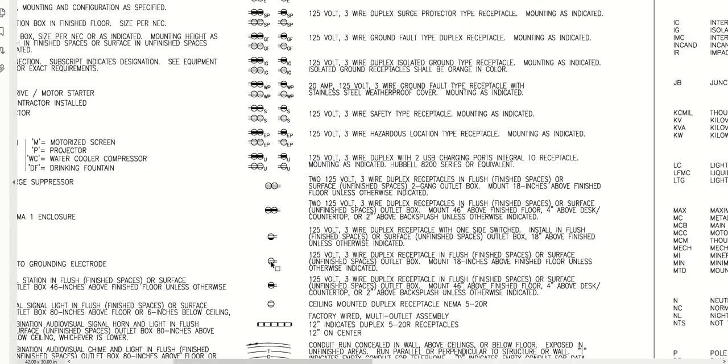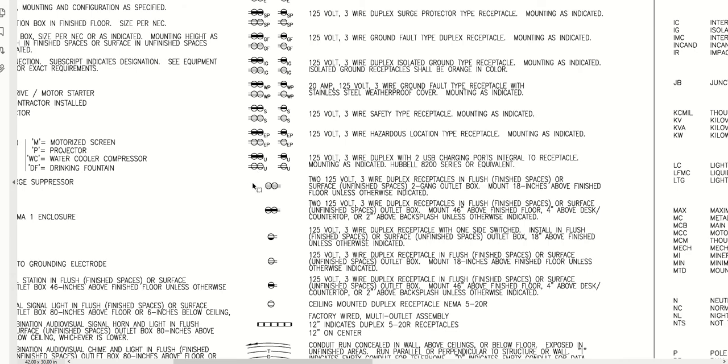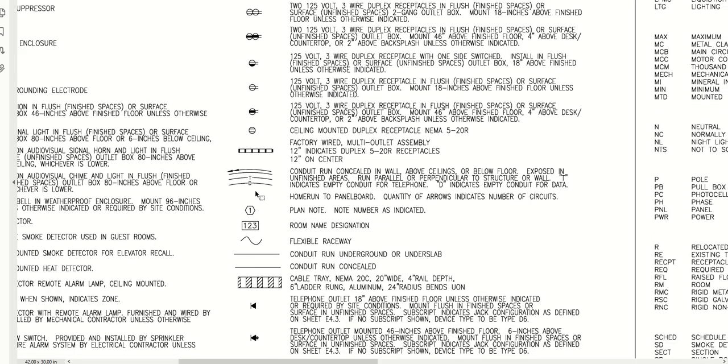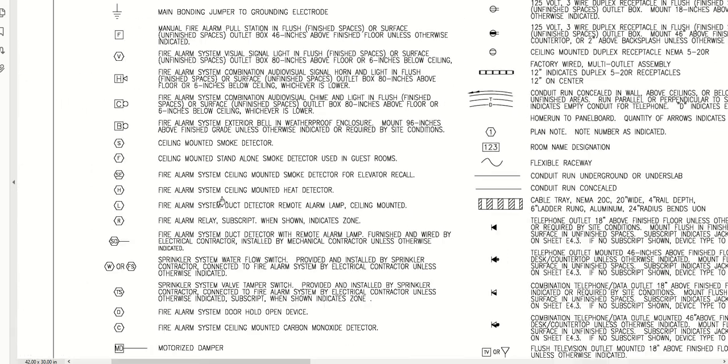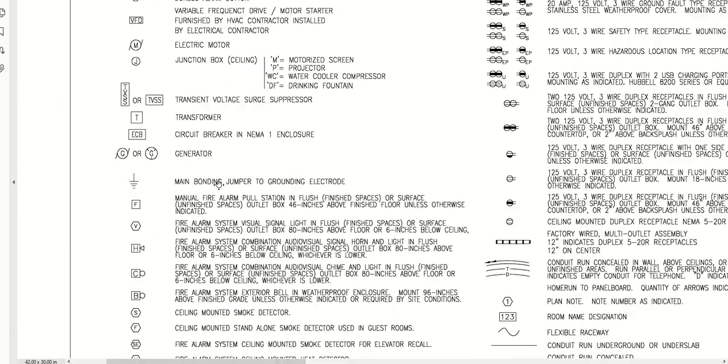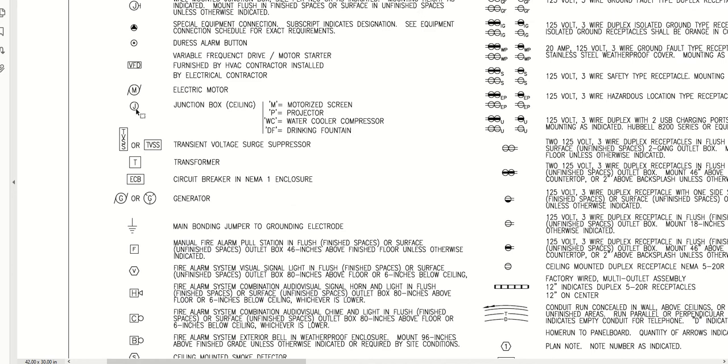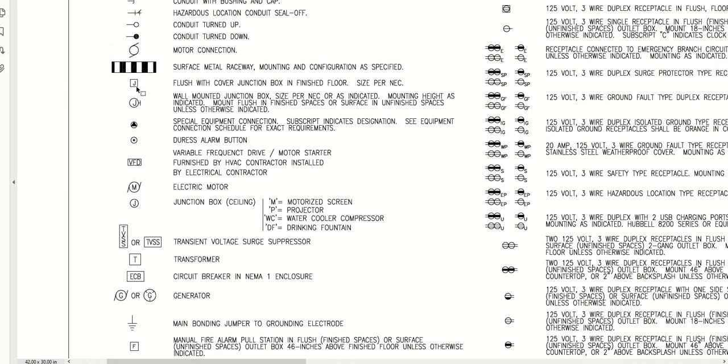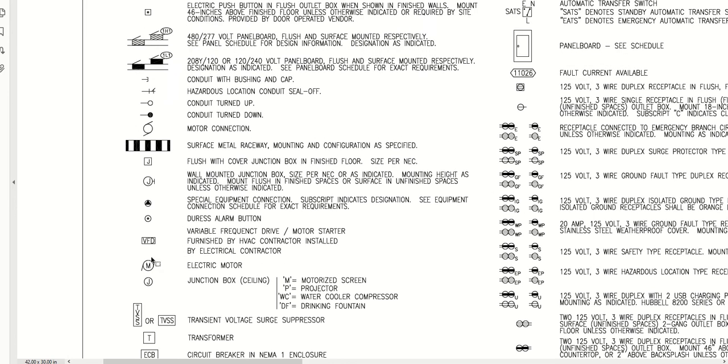We have our general receptacle outlets—these are at 18 inches. If it's filled in, it's at 46 inches. If it doesn't have the little divots, it's a ceiling mount. We have tags for weatherproof, isolated ground, ground fault, and we have junction box connections for floor, wall, and ceiling mount junction boxes, transformers, and all the like.